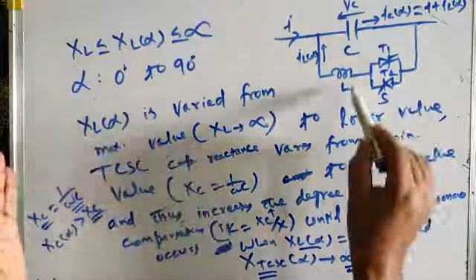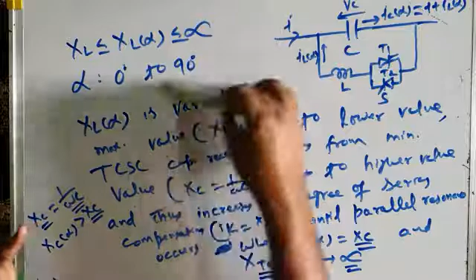Okay, so starting from alpha equal to 90 degrees for TCR, the TCSC reactance is minimum capacitive reactance, that is equal to Xc equal to 1 by omega C. Then decreasing alpha from 90 degrees to a lower value, the TCR reactance decreases, and since L and C form a parallel LC circuit, the overall TCSC capacitive reactance increases. It becomes greater than XC until parallel resonance occurs when XL alpha is exactly equal to XC, and when this happens, the TCSC total capacitive reactance becomes infinite, okay, which is again an undesirable thing.